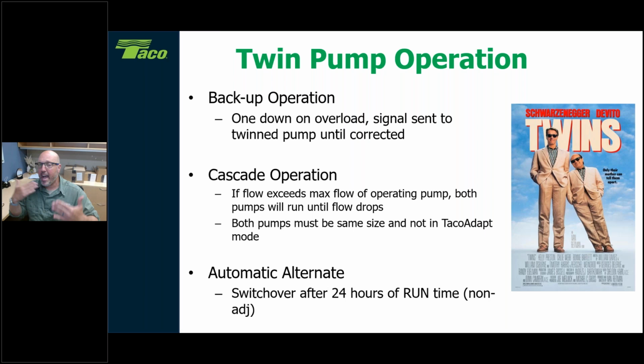So this way you have both circulators getting an equal life out of them, and making sure the second one is always going to be in operation. You never want that first one to be running for 10 years, and all of a sudden one day, hey, let's turn on the second one, and the second one doesn't run because it's never been turned on in 10 years. So that's automatically built into the circulators themselves.